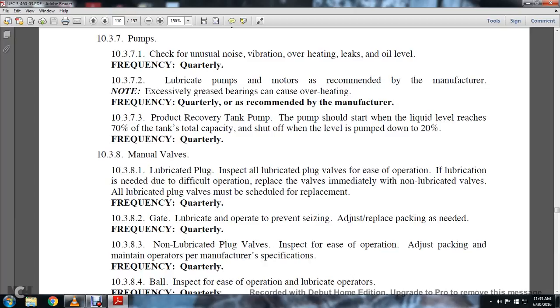10.3.8 Manual valves, lubricated plug installed. On lubricated plug valves, if lubrication is needed for difficult operation, replace the valves immediately with non-lubricated valves. All lubricated plug valves must be scheduled for replacement. Frequency is quarterly.